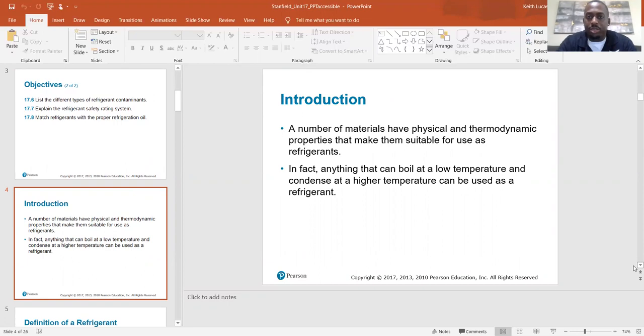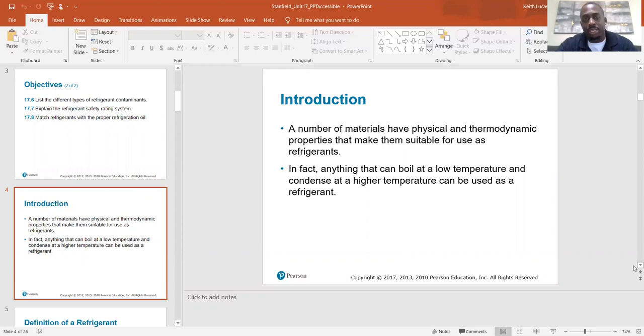A number of materials have physical and thermodynamic properties that make them suitable for use as refrigerants. In fact, anything that can boil at a low temperature and condense at a high temperature can be used as a refrigerant. Inside the system it's boiling in the evaporator coil at 40 degrees, evaporating and then condensing at a high temperature outside at the condenser, which is going to be 30 degrees above the ambient temperature.